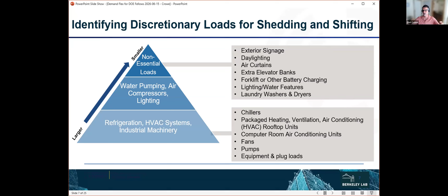The next best would be large loads with minimal disruption. Typically, if you have HVAC set points that you can adjust for a few hours, there will be some disruption, some impact on occupant comfort. The intent is that you can communicate clearly enough and the benefits are high enough that it's a disruption worth having, 5, 6, 10 times a year.